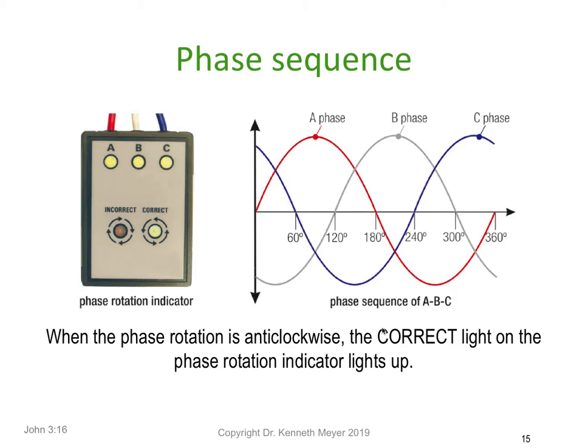One of the tools we use to make sure our phases are connected and rotating in the right order — because it's very easy to get A, B, and C mixed up — is a rotational phase indicator. You can see it has red, white, and blue connections. You just connect it to each of the phases, and if they're rotating in the correct direction the correct LED will illuminate. If it's incorrect, the red LED will illuminate. When the phase rotation is clockwise, the correct light on the phase rotation indicator simply lights up.